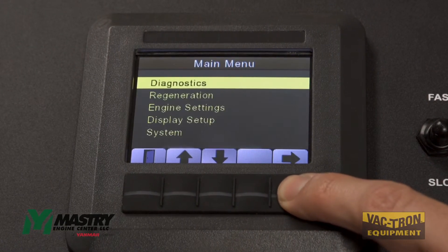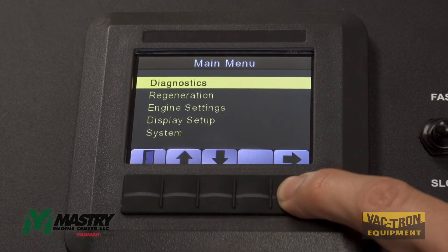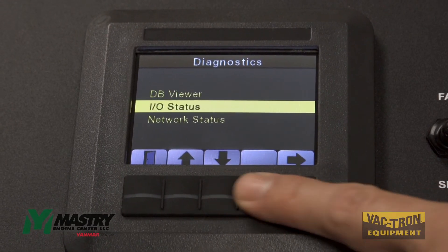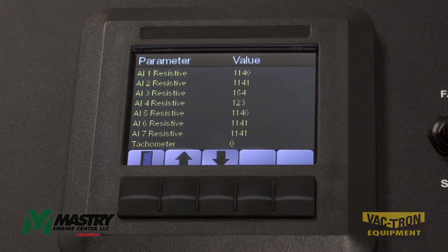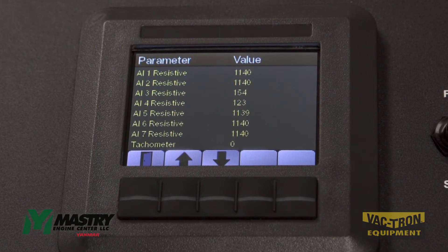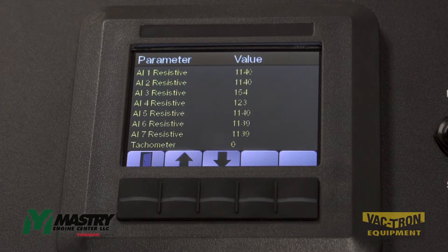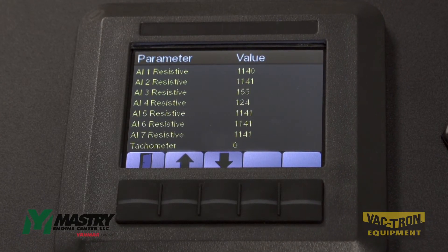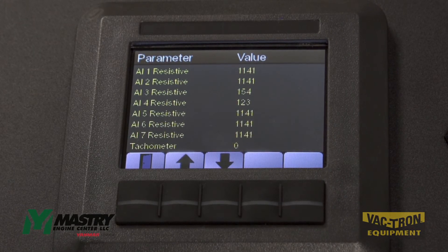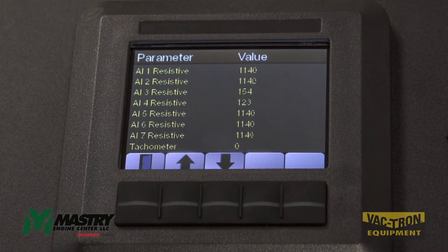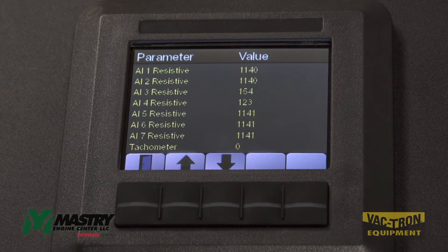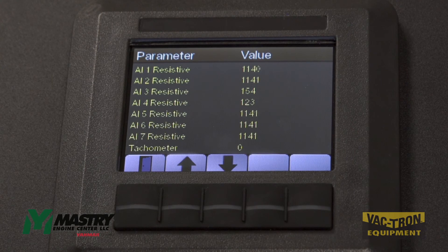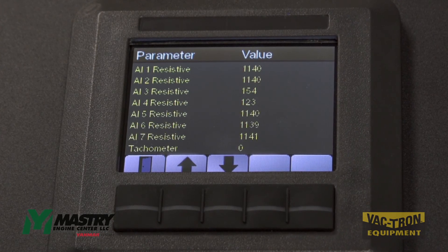To get more information about the analog inputs to the panel, you can enter the main menu, then the diagnostics menu, and then IO status. Analog input 3 is the fuel sender, and analog input 4 is the oil pressure sender. The fuel input, analog input 3, should read between 33 and 240 ohms if it is functioning correctly. Analog input 4, the oil pressure, should read between 10 and 180 ohms if it is functioning correctly.